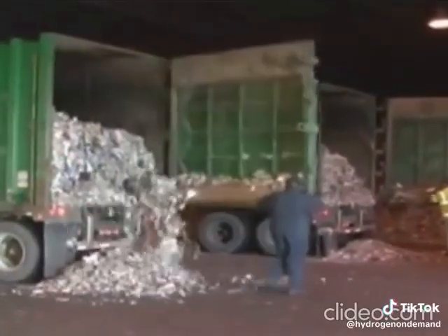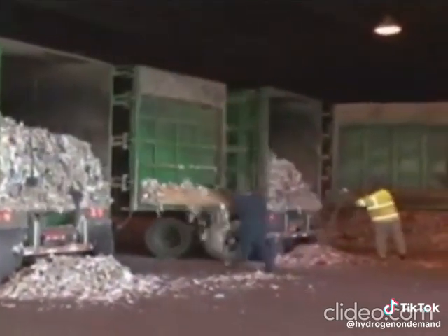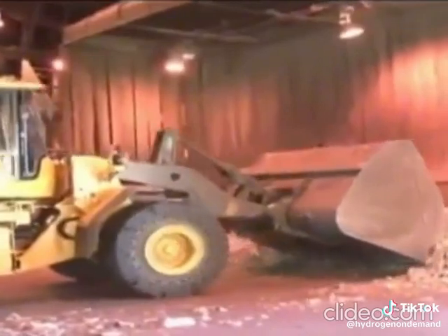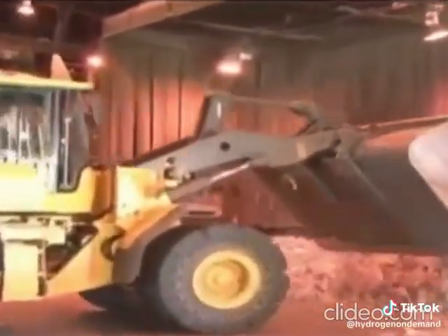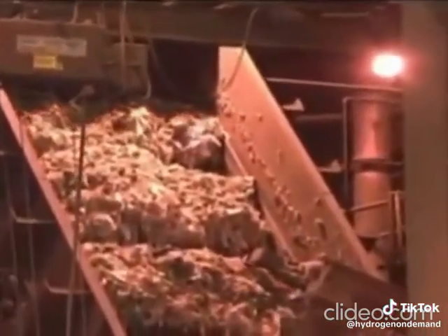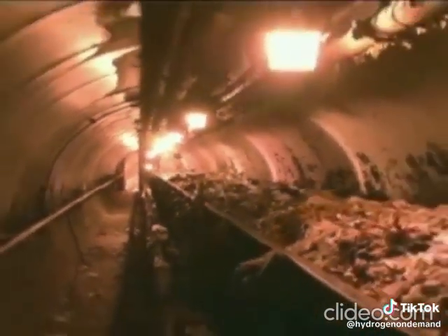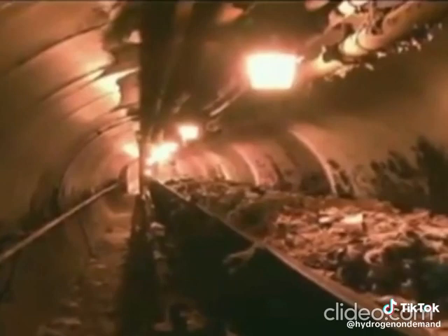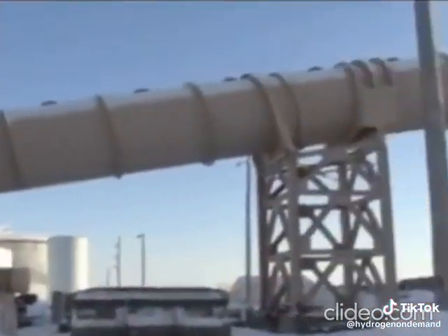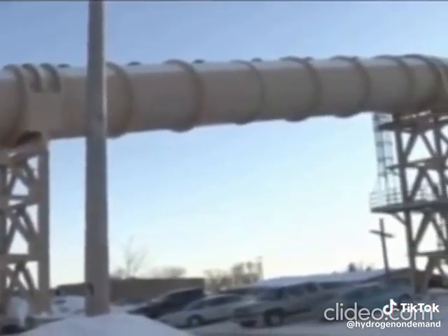Every day we receive 50 to 60 truckloads of fuel from the Elk River Resource Recovery Facility. It includes a conveyor system that brings the fuel into the plant. There's a walking floor system that feeds an incline conveyor, which then feeds a belt conveyor, which runs in the tube that you see going across the railroad track into the top of the power plant. That's a belt conveyor that then feeds our distribution system within the plant.